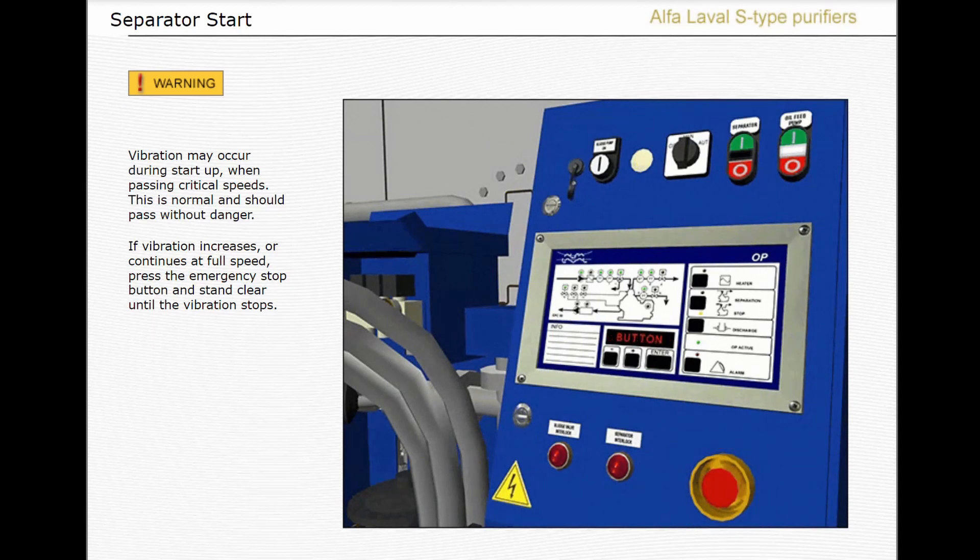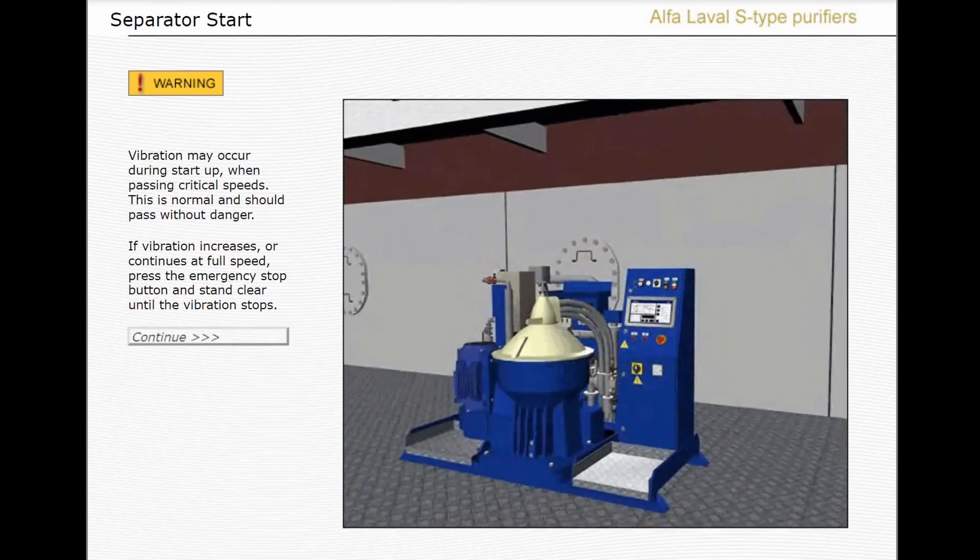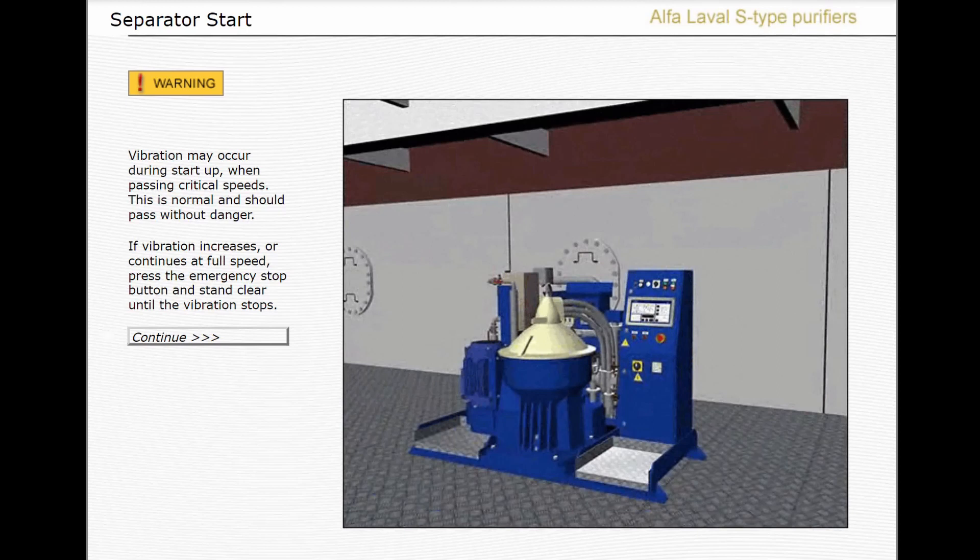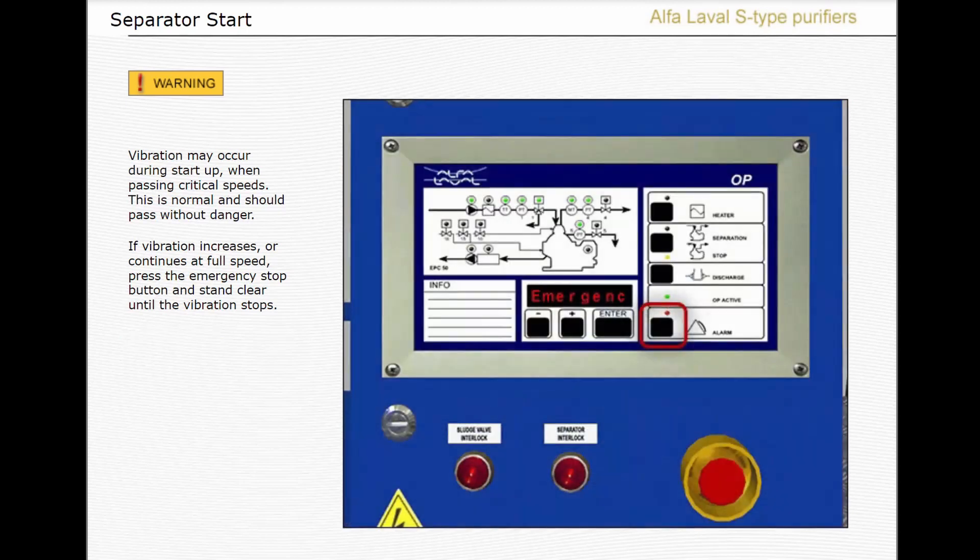The separator, feed pump, and heater are stopped when the emergency stop button is pushed. Once the zero speed signal has been received, the alarm reset button can be pushed. The message 'switch power on off' will be displayed. This refers to the EPC power inside the control cabinet. The cause of vibration must be determined and corrected before starting again.